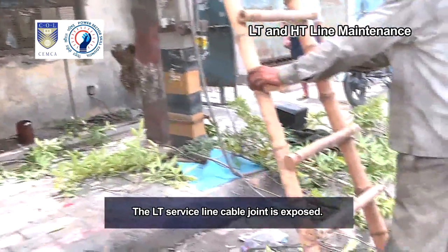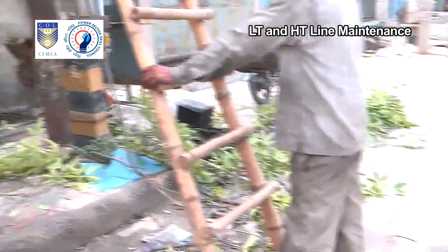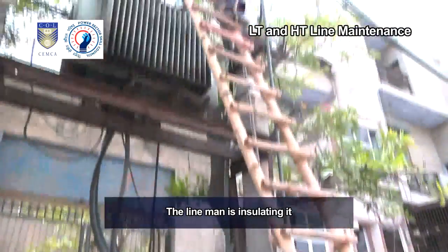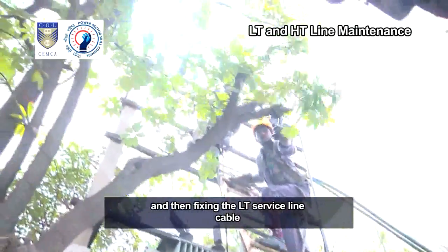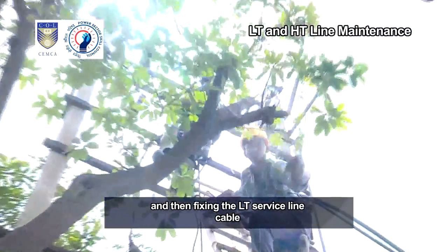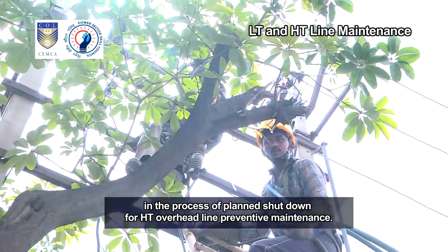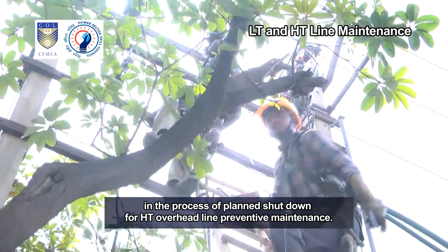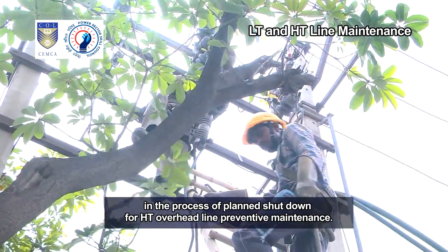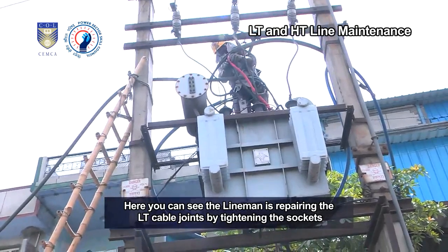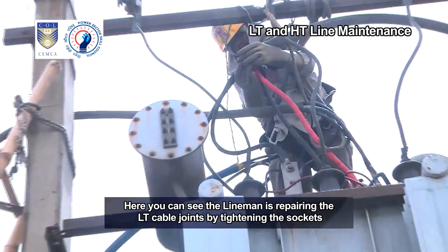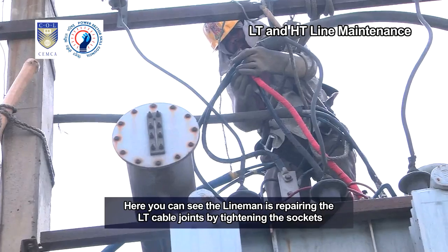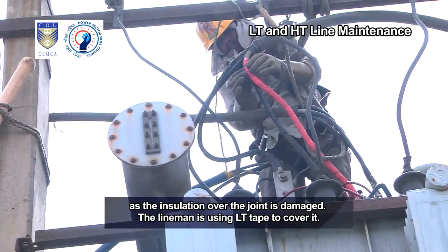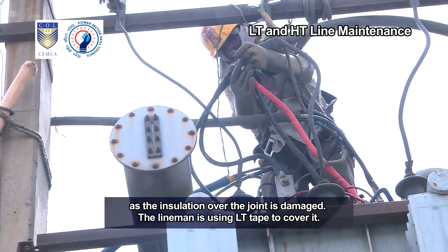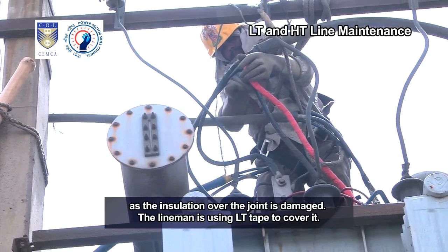The LT service line cable joint is exposed. The lineman is insulating it and then fixing the LT service line cable in the process of planned shutdown for HT overhead line preventive maintenance. Here, you can see the lineman is repairing the LT cable joints by tightening the sockets as the insulation over the joint is damaged. The lineman is using LT tape to cover it.